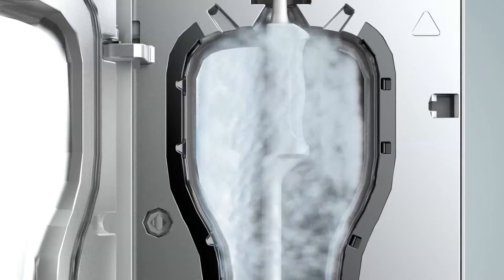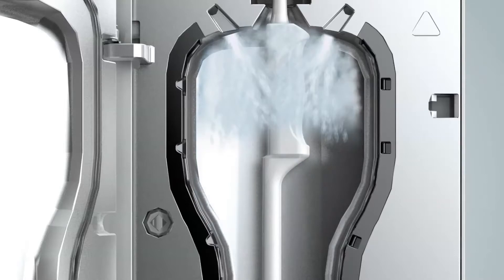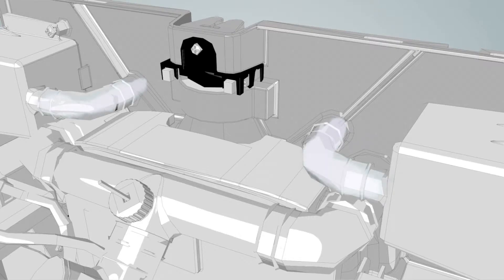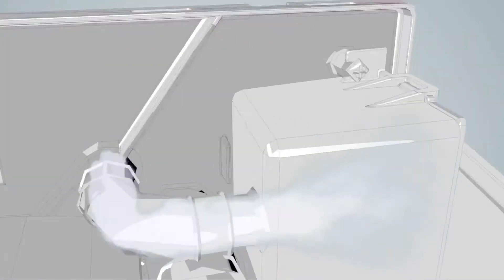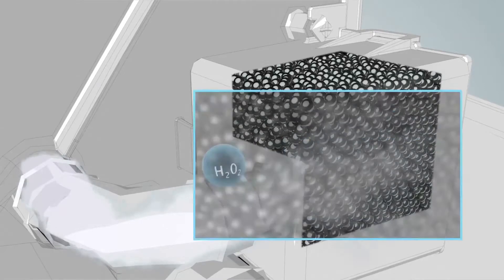After disinfection, residual hydrogen peroxide is blown out of the chamber and passes through destructors, where it is broken down into environmentally friendly water and oxygen.